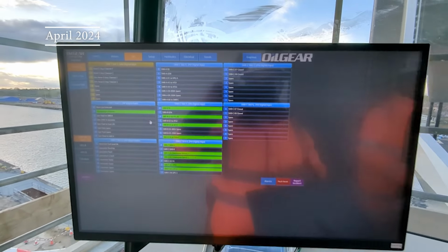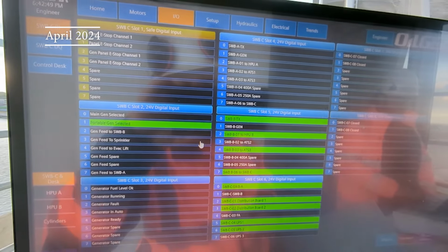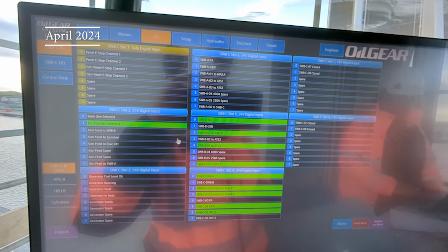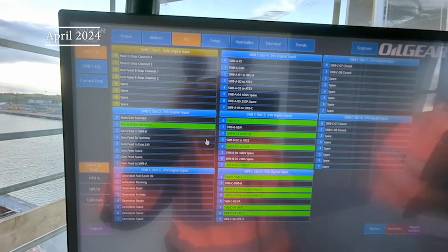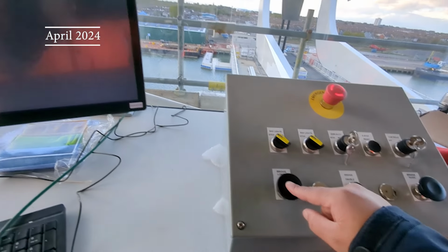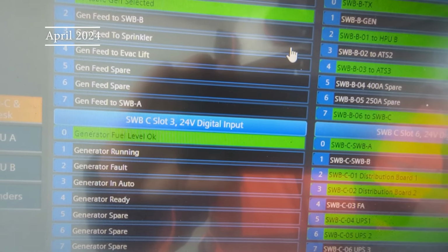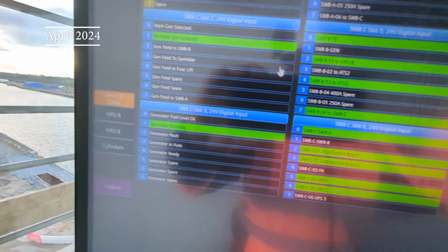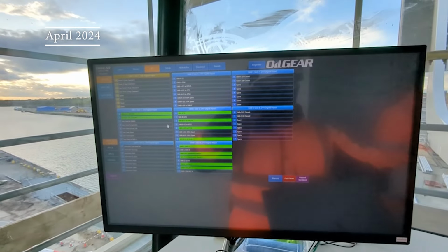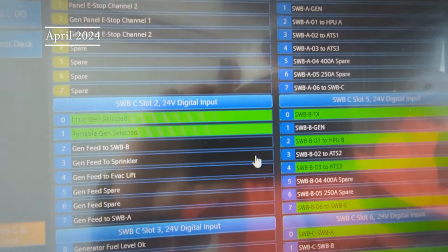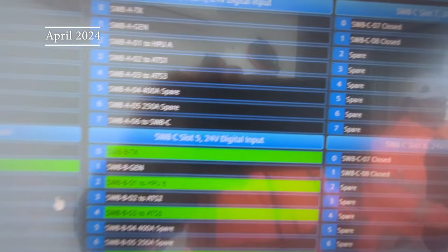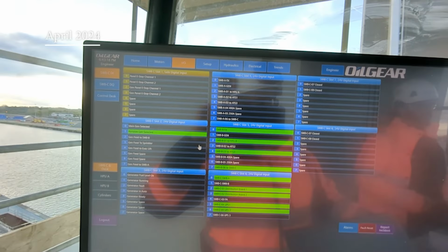At the moment I do check encoders. Ivor, there seems to be a problem. So I'm on the SWBC card, IO screens, and if I hit the bridge lower button, the generator fuel level okay input comes on. So I guess we've got an addressing problem. If I hit the bridge raise, then the generator running signal comes on. If I turn controls on or off, then I get the main generator selected. So I'm guessing that's probably why that card also isn't currently working. So yeah, bit of an issue here.